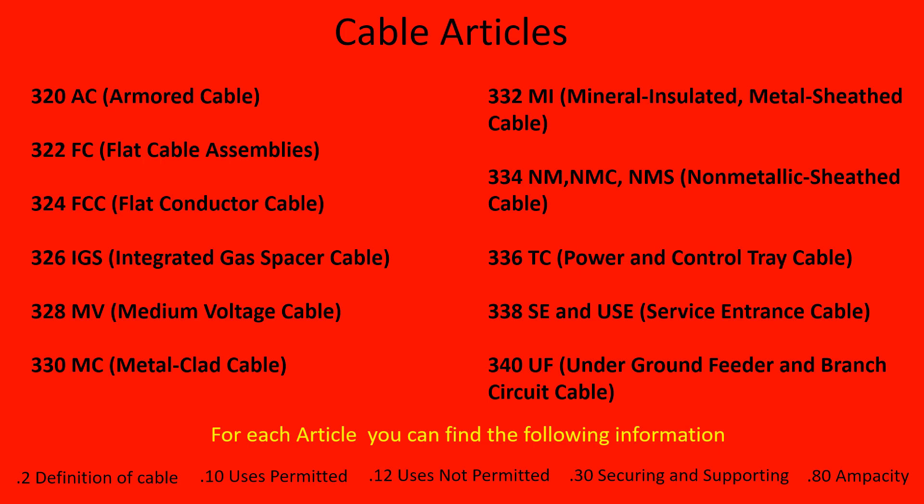To recap: if you have a dot-two, it's going to tell you the definition of each one of those cables. A dot-ten tells you the uses permitted. A dot-twelve tells you the uses not permitted. The dot-thirty tells you how to secure and support it. And the dot-eighty tells you the ampacity — how you deal with the ampacity of that conductor.